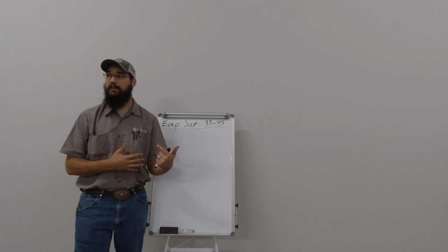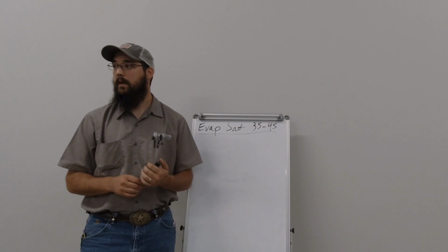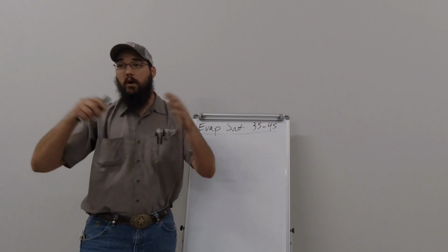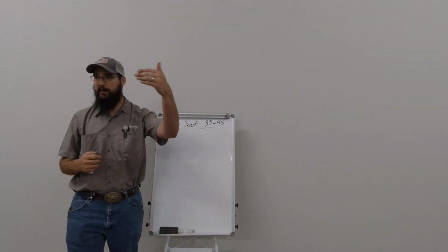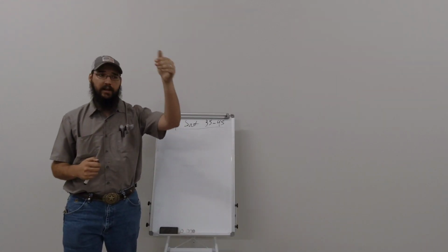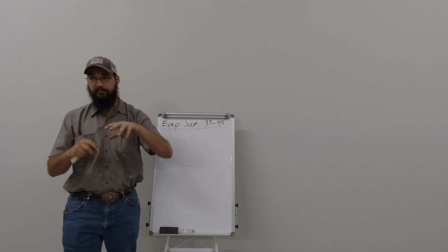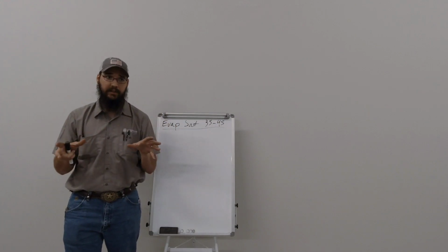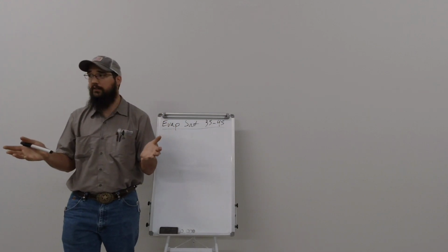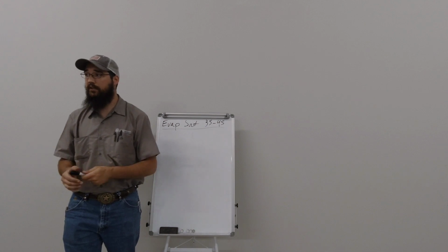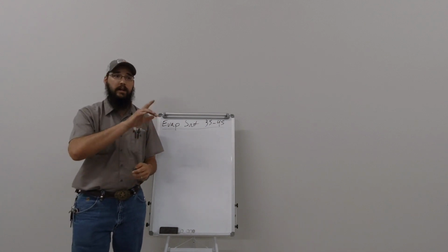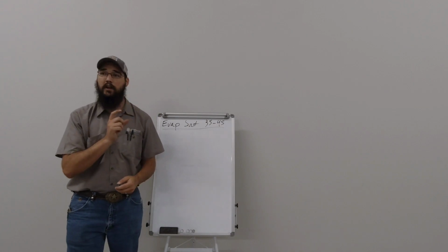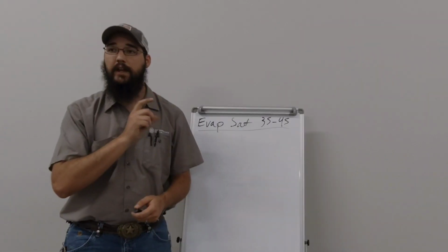All of that ties back into saturation. So I'm glad you brought it up. Most of the time, if you're using digital apps or even your pressure manifolds, if the analogs have the 407 on there, that's automatically built in. You don't have to put a whole lot of thought into it. But if you do have a system that doesn't automatically generate that for you, or say the analog gauge doesn't have that temperature scale for 407, you have to do that yourself.